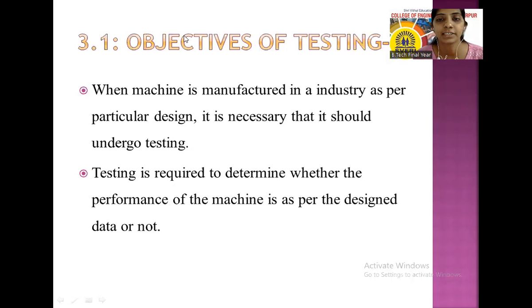To get the performance of a particular machine, testing is very necessary, and testing is important to get various characteristics of machines, and also get input output, and the efficiency of that machine. By getting that data, we have to check if that data is matching with the design data, or with Indian standards, or falling within the permissible limits given by the Indian standards or not.